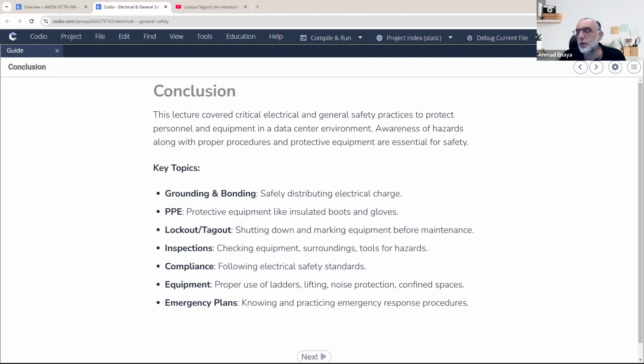How to check bonding? Good question. I have never come into this, but I would say maybe short circuit. Many meters have a short circuit check. If the bonding is working as it should be, and this is your server connected by a cable to the chassis, how much do you think the voltage should be between the chassis and the rack? Logan is correct, it should be 0.